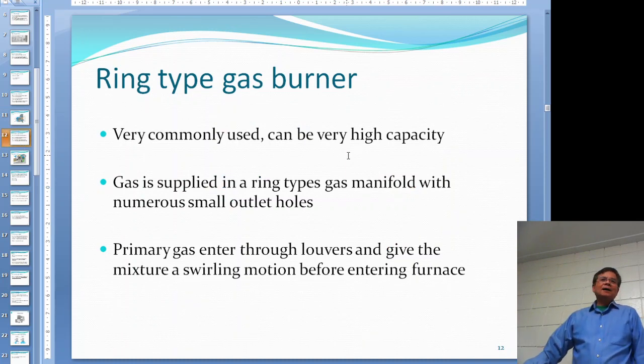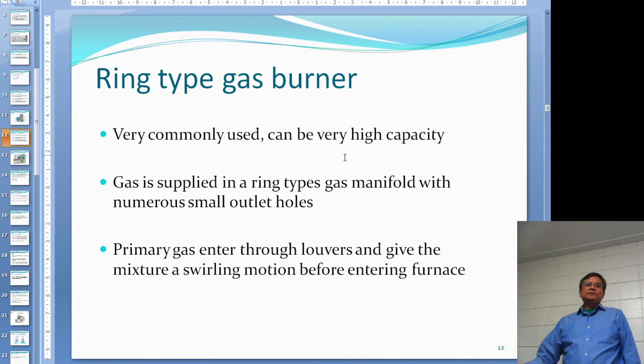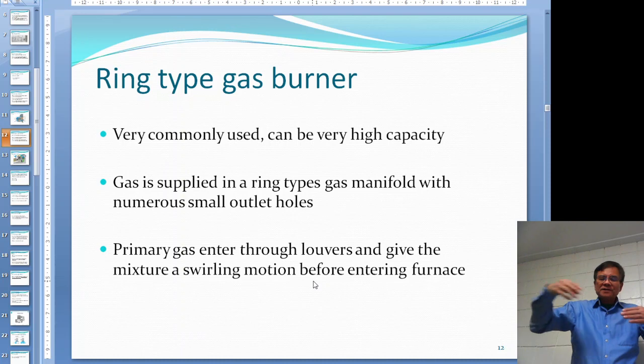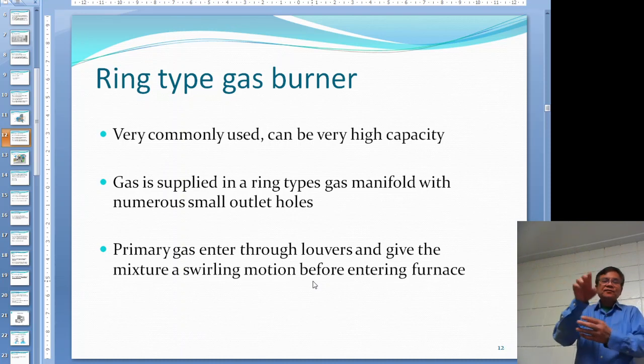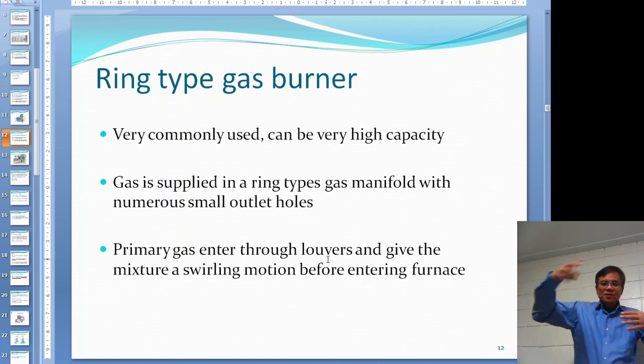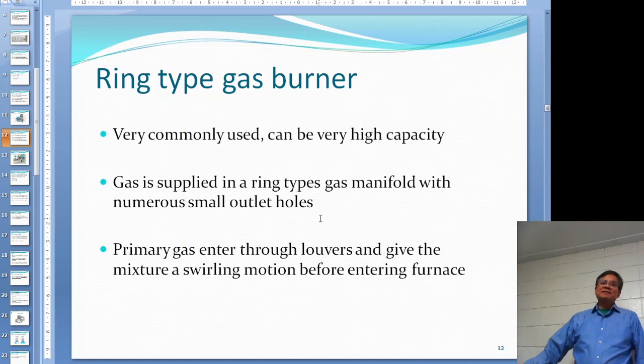The ring-type gas burner is very common, and I think ours in the lab is a ring-type as well - really high capacity. The gas is supplied to a round gas manifold, and each one has small holes. The primary air goes through a louvre, and the reason for the louvre is that when air passes through it creates a swirling motion. This turbulence - remember from Chapter 1, the three T's included turbulence - makes the air and gas mix up better.